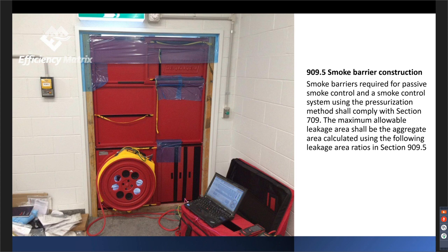Talks about the tightness of the smoke barrier, and smoke barriers are required to be smoke tight, obviously, although there's always going to be a certain amount of leakage, because the first thing that we do when we build this beautiful full height outside wall, 1-hour wall, is poke holes in it with doors and windows and ducts and conduit penetrations, etc.